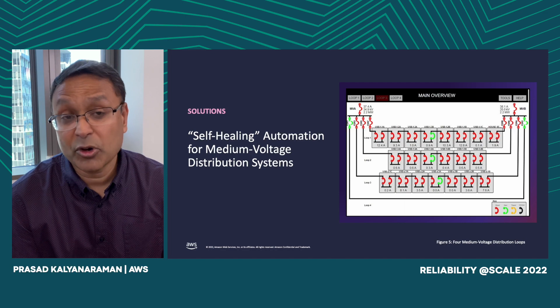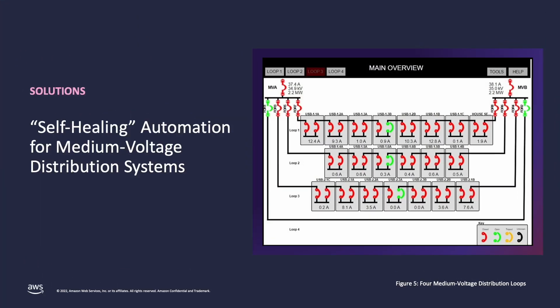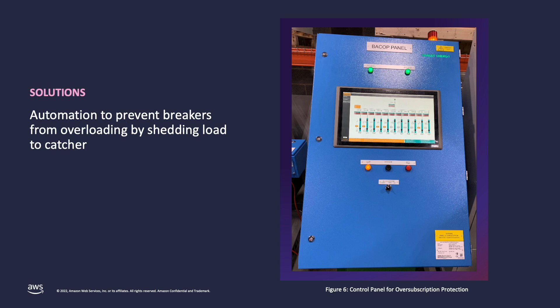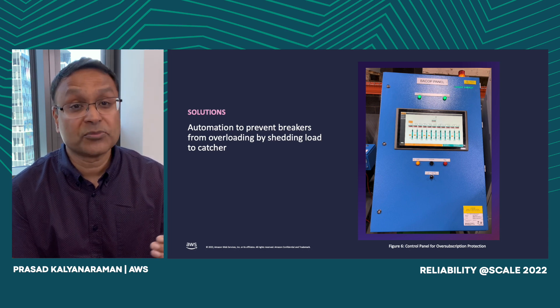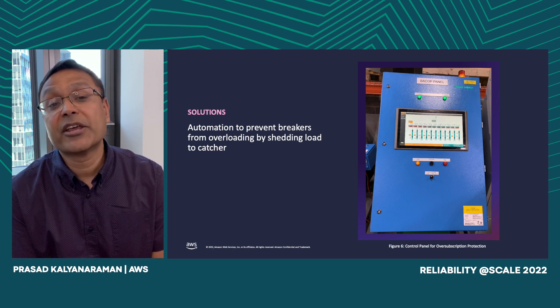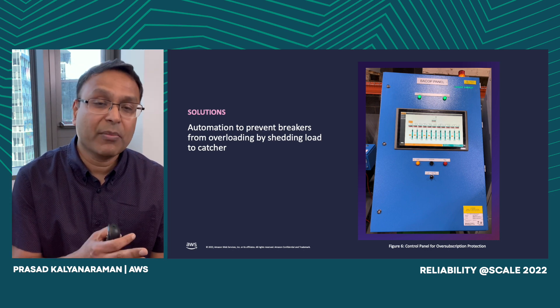Some examples of self-healing systems we've built: we built automation that automatically switches between two medium voltage lineups for a particular feed. We also built what we internally call a BACOP system to prevent overloading — it automatically sheds some load to catcher. We pre-select a set of racks that can automatically move to catcher if we see any oversubscription, ensuring we never drop IT load. This in-house automation moves power from primary to backup automatically.